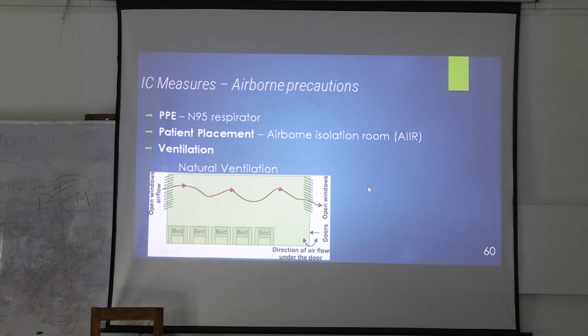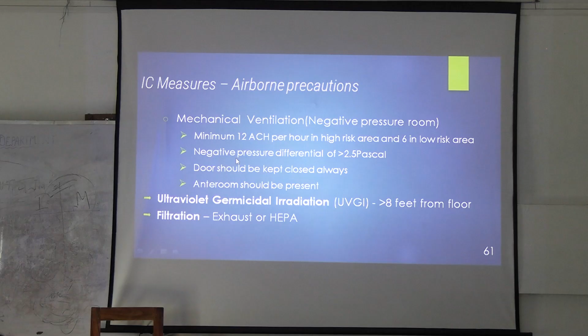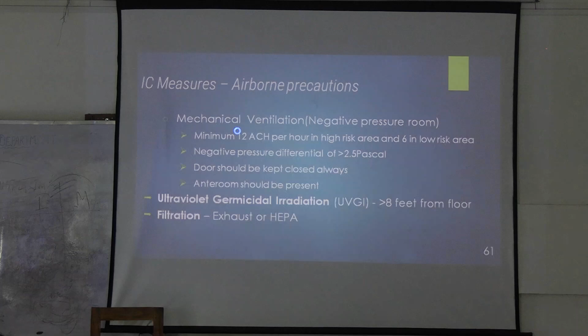These are the important things that you have to remember. Plus, if there is negative pressure in the room, minimum air changes in a negative pressure room, in case of tuberculosis, should be minimum 12. How much is this in OT? In OT, there are minimum 20 air changes per hour, out of which 4 are at least fresh. Okay? Here, they are 12. Okay. That was about transmission-based precautions.